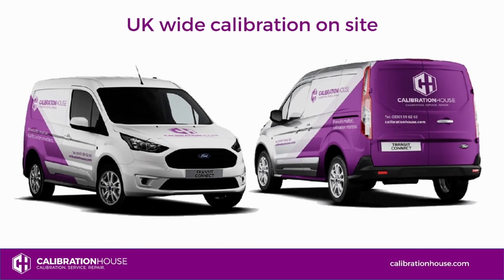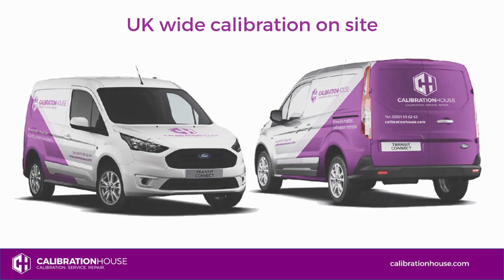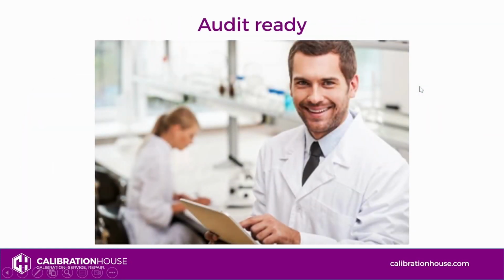Alternatively, and wherever possible, we can bring our calibration lab to a customer's premises. Our engineers can attend anywhere in the UK and Ireland, and they bring all of the equipment required to perform the calibrations on site. They just need space and power and the units requiring calibration, and that means there is very little downtime for the customer. The calibrations are completed and the unit goes straight back into use. In either scenario, we pride ourselves on our service, and ensuring the customers have peace of mind that their equipment is performing well and is accurate, and that they have everything they need for any audits.